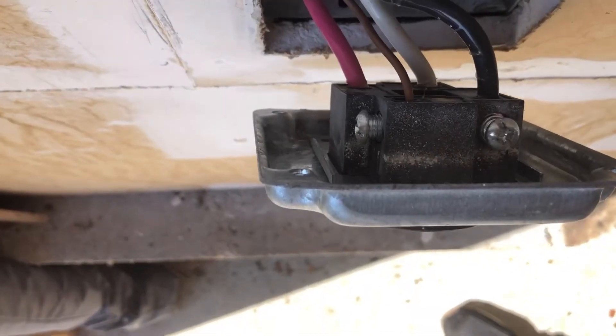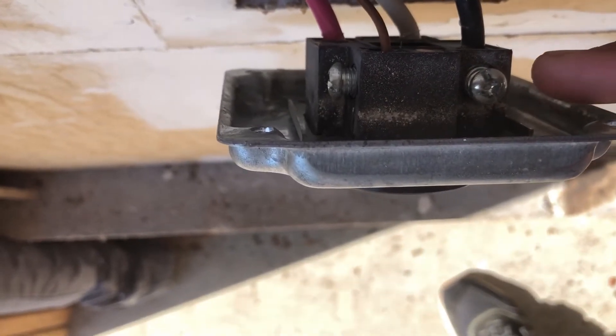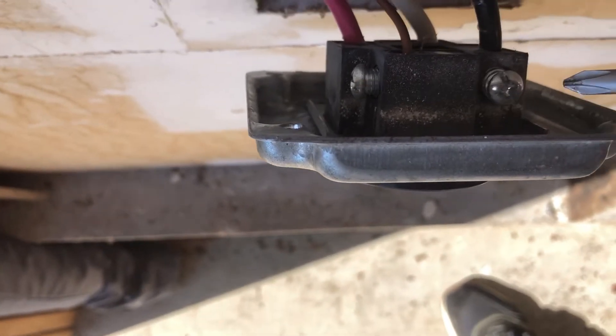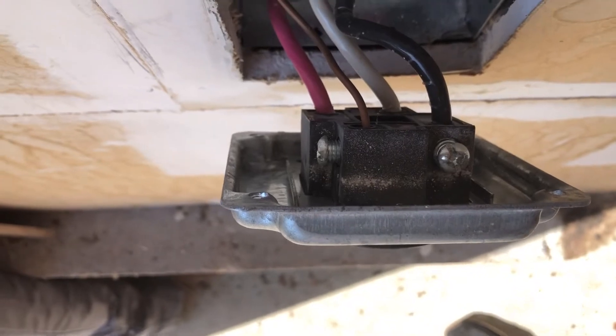Alright, take a look. What we're going to consider here for the loose wiring is these fasteners that tighten down on each of the wires. There's two up here that you can see and then there's two more on the bottom. We're just gonna tighten them down — I suspect that they're loose.